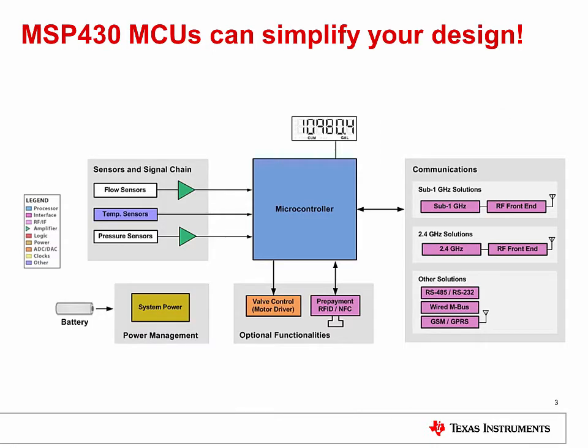If you take a look inside a flow meter, you'll find several key pieces. Flow sensors for sensing flow — for example inductive, magnetic, or optical sensors. A signal conditioning circuit for filtering or amplification to convert the analog input into a signal suitable for processing. And a data processor or controller to receive a digital output of the analog flow information via the analog-to-digital converter, process the information, log the reading with the meter, and communicate that information through a dial, display, or wired wireless communication.